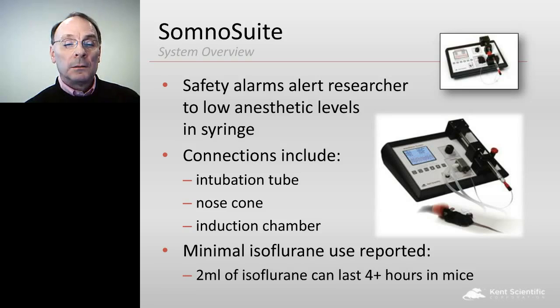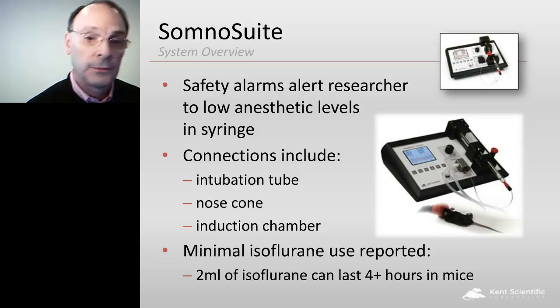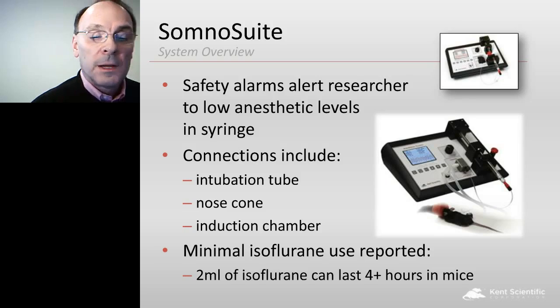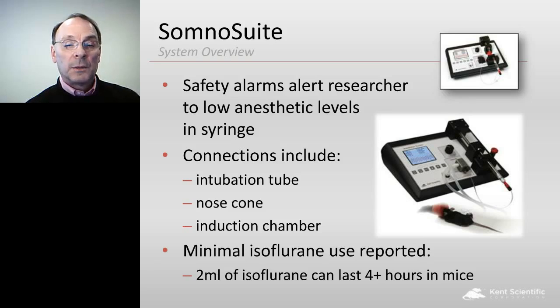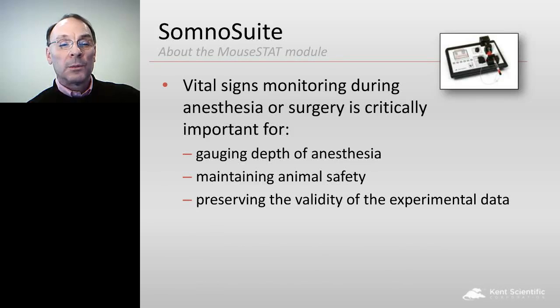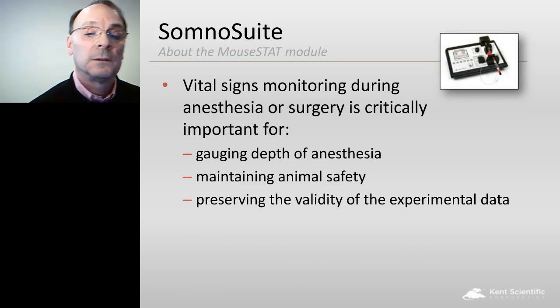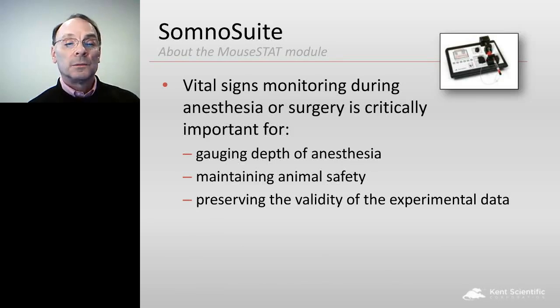Typically, I like to say that you'll use less anesthesia in a mouse during a full 4-hour experiment than you would filling a funnel-filled standard vaporizer. So typically, we use about a half ml, anywhere from 0.3 to 0.5 mLs per hour to anesthetize a mouse. And a standard vaporizer uses much, much more than that, even 10 times or more.